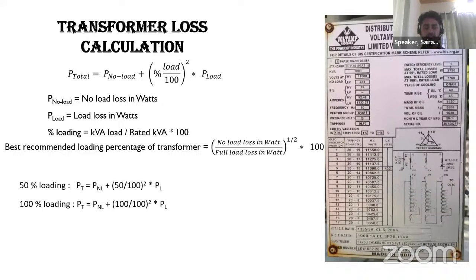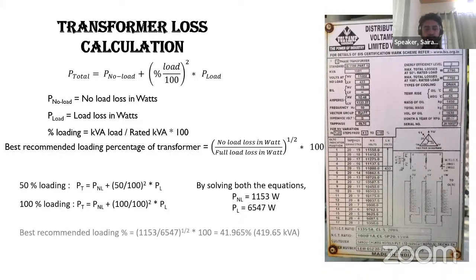At 50% load, you have to frame the equation as per the formula described above, taking the total loss as 2790 at 50% load, and for 100% loading you have to take 7790. These values will be replaced in the equation. If you solve both equations, you will get the no load loss as 1153 watts and the load loss as 6547. As you have the load loss and no load loss, you apply them in the formula and get the best recommended loading percentage. It is 41.96%.